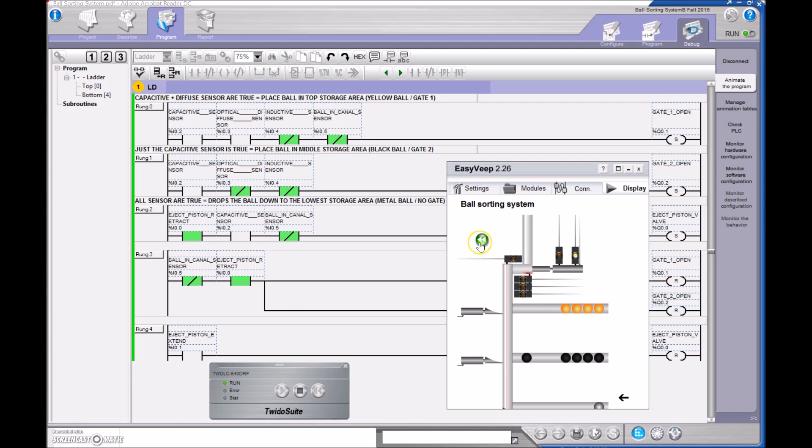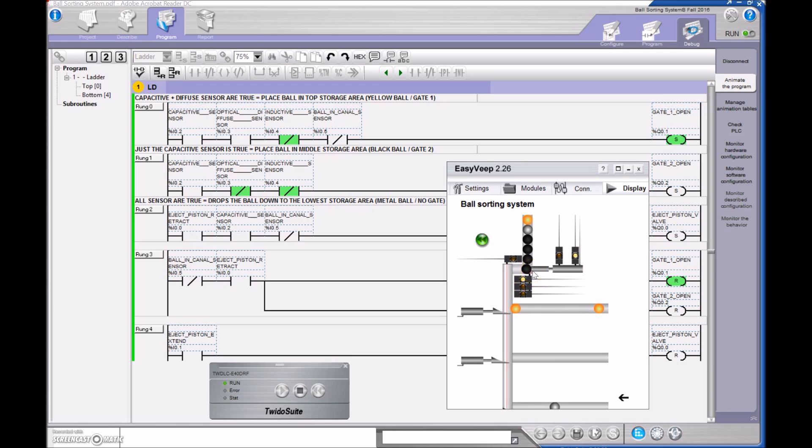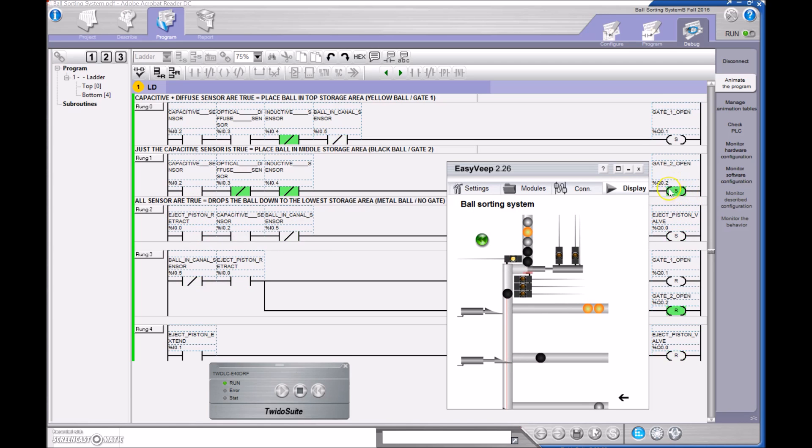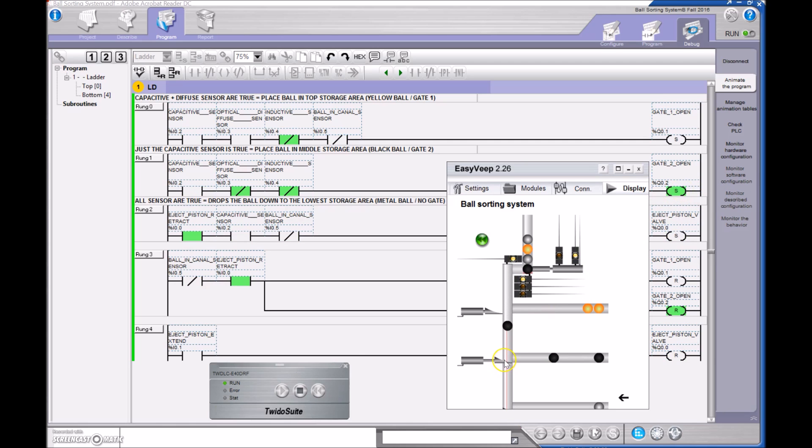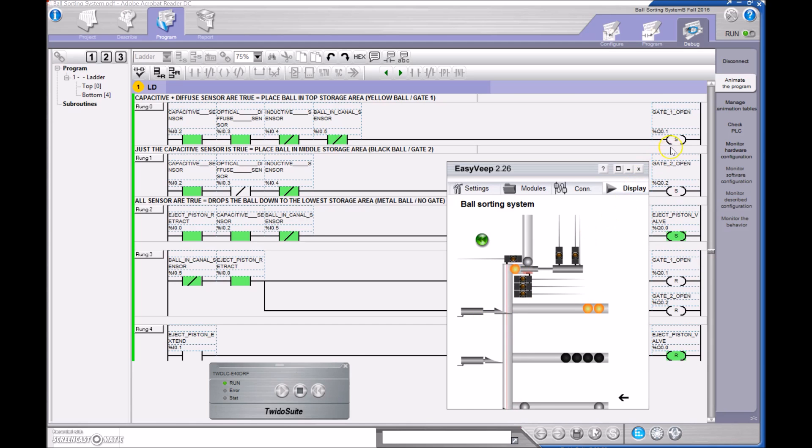But everything's working all right. The black balls are all going into the center. Yellows are going to the top. And again this one's going to go to the center. If I reset this one more time, then I'll take your attention over to the PLC program. You can see that right here, this is extending this cylinder right here. So this is true right there, extending it and dropping it down. There we go. Now my second gate is right here. So let's take a look at this guy. You can see that that is activated right now, meaning that this is out. The black ball is going here. Again, this black ball activates this guy. Now it's deactivated. Nothing's activated right now and the silver ball goes down. And the first gate is right here. So when this guy activates, then moves my yellow ball over. Excellent.